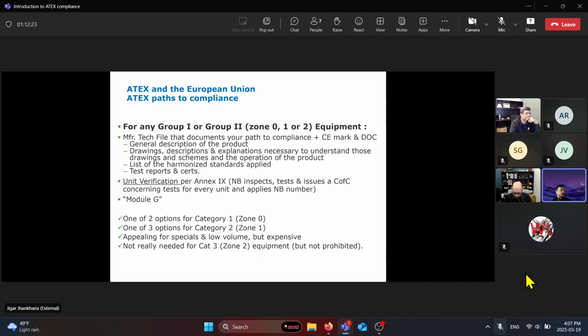So again, this is just discussing the different options for unit verification or type certification. But the technical file for a type certification would include the CE mark, notified body number, and all of that. The report would be a bit different for a unit verification as compared to a type certification. When we do a type certification, we upload that information of your company on our website under the client database, which references the ATEX certificate, which is accessible for any of your clients in the world, similar to your North American certification. But for IECEx, it would be available on the IECEx scheme website, where you can search up any IECEx certificate.